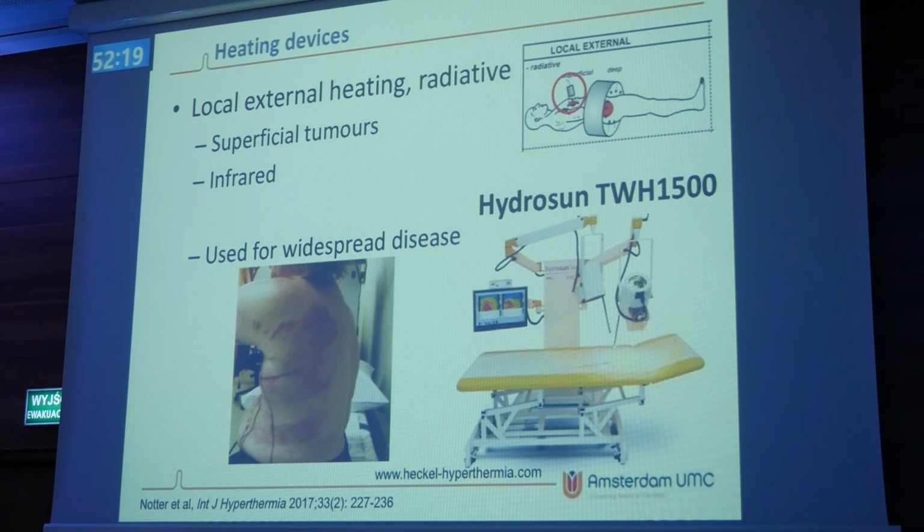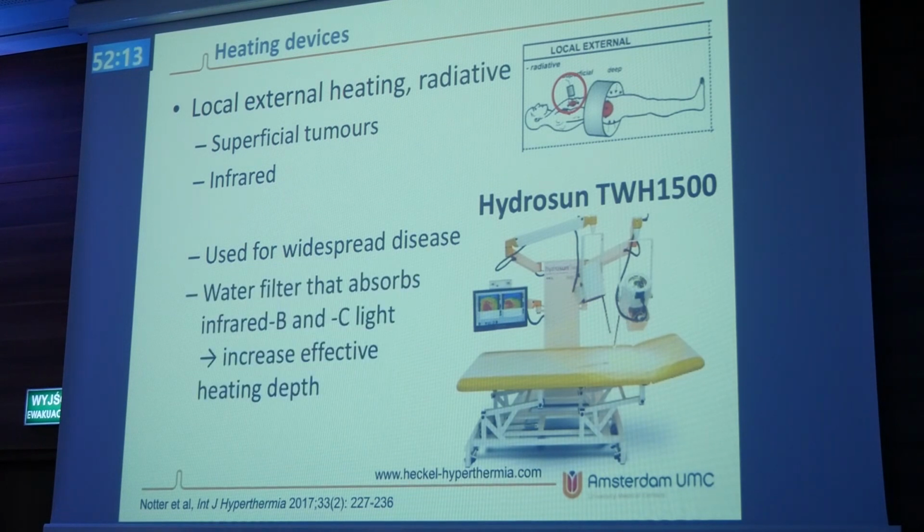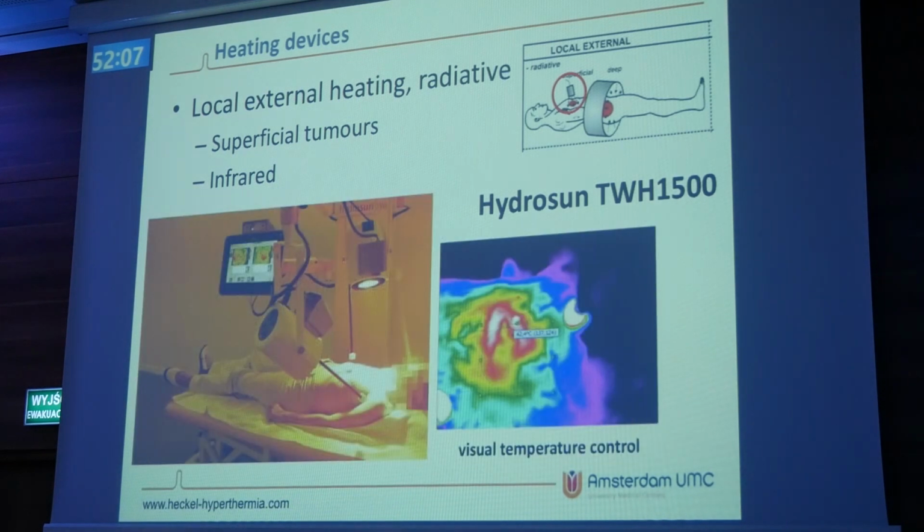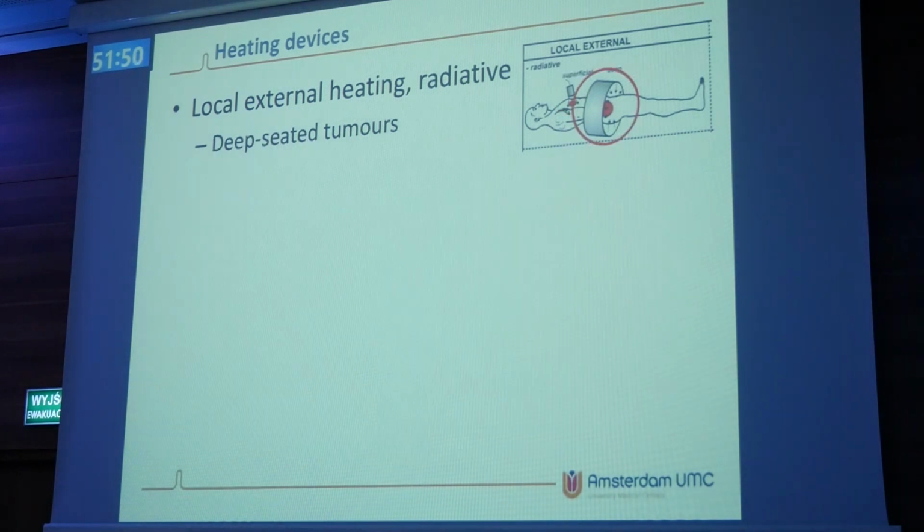And instead of electromagnetic waves, in this case infrared radiation is used, with a special filtering to increase the effective heating depth. And this is what it looks like during treatment. So in this case, no water bag between the patient and the applicator, which also means that you can use an infrared camera to actually monitor the temperature distribution during treatment.